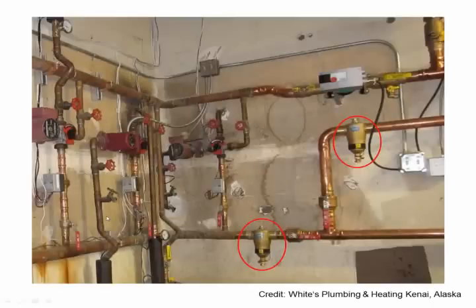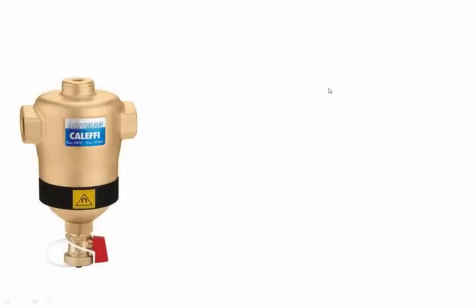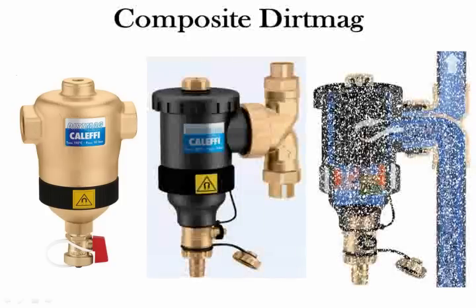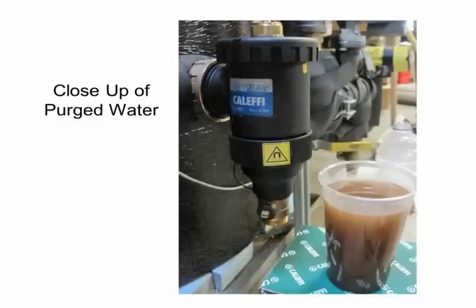This is probably a retrofit from up in Alaska, White's Plumbing. And so he perhaps put in some very modern equipment in here to replace maybe the older equipment. That modern equipment you don't want to have caked up with ferrous oxide. We also have ECM pumps here that we want to protect from ferrous oxide. And we have a whole line of these, as you can see, both dedicated dirt separators and combination air and dirt separators that have that magnetic collar.